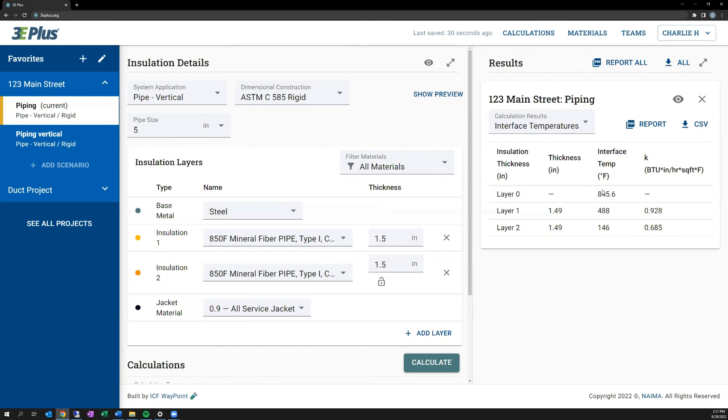I'll hit calculate. And once the results appear, you'll see that layer zero says the result between the pipe and the first layer, and that's pretty close to the process temperature as it's just at the outside surface of the pipe. And then layer one is between insulation one and insulation two. You can see it's dropped quite a bit. And then layer two is outside of insulation two. Now, this might be useful if you have a high temperature application and you want to see how much the initial layer of insulation that might be rated for a higher temperature brings down the temperature before moving to a lower cost material that won't be exposed to as high of a temperature so it could be used. And this software will give you results particular to each type of insulation that you're specifying.